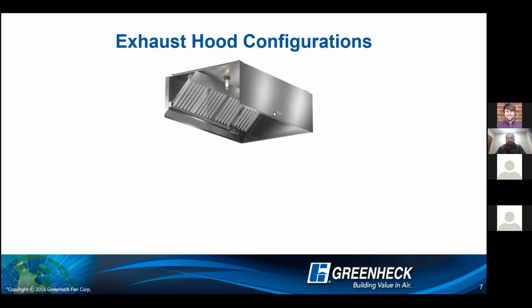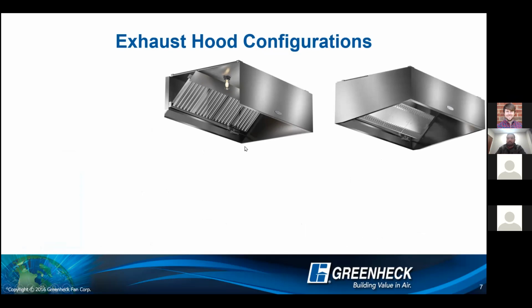So moving on to the different exhaust hood configurations, we're going to start with our basic configuration, a wall canopy exhaust hood. This would be a standard 24 or 30-inch tall wall canopy exhaust hood hung 80 inches off the finished floor per ADA requirements. If you have a low ceiling application, we can do a tapered front hood. That can be tapered in 18, 15, or 12-inch front heights, and that reduces the overall front of the hood so that you can hang it in a low ceiling configuration.